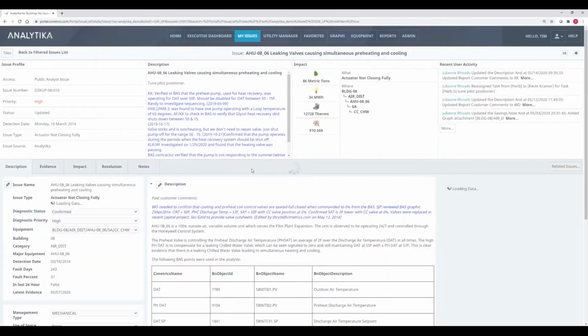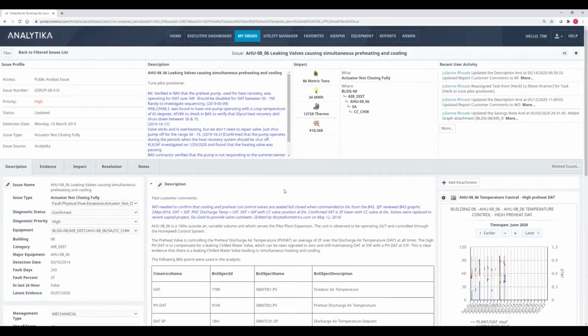So this is the detail page for that particular issue. That issue was air handler 8.6 had leaking valves causing simultaneous preheating and cooling. Here's our recommendation: the pilot positioner needs to be tuned.